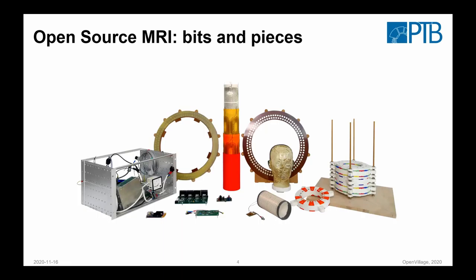After all this cascade, we have our RF pulse that basically tilts our magnetization in this direction, and then it starts to rotate. Now if we want information on the location where the signal comes from, we need something we call a gradient — a variation of the magnetic field. Here's a gradient coil, and for that we need amplifiers again. With this gradient coil, we can in three dimensions change the magnetic field — here it rotates a little faster, here a little slower. We then Fourier transform that, so we have frequency information in space and we get our image. That's MRI in a nutshell, and all the components needed.